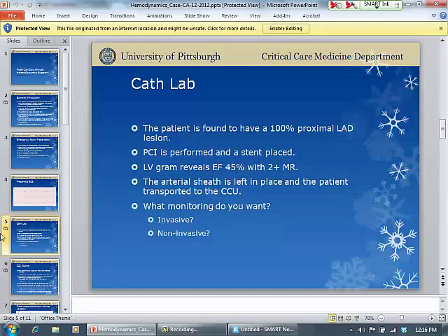And that will still be a calculation of the stroke volume. So if anything, it'll still be accurate, assuming, of course, that you have a waveform that you can interpret. In really bad cardiogenic shock, the waveform can be so depressed that the device can't even calculate it, and the pulse pressure is less than about 15 millimeters of mercury. The device turns off and won't even report a number, even though it can calculate it. So the tone is not as big an issue as you would think, and I'll show you why.